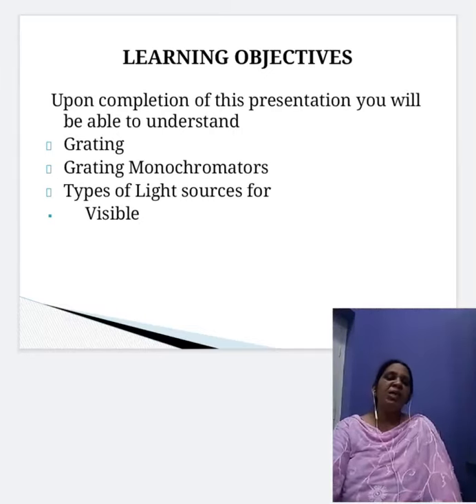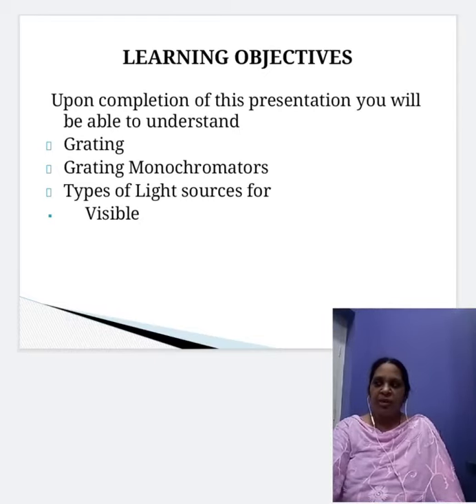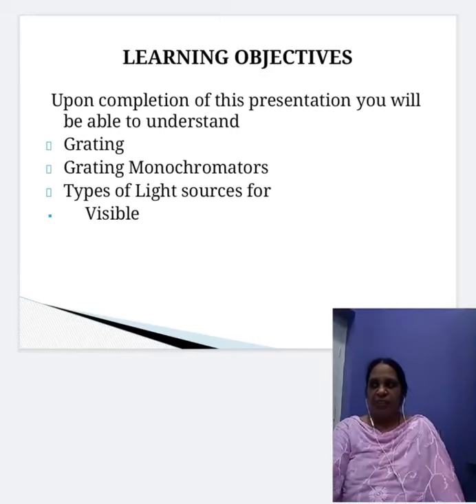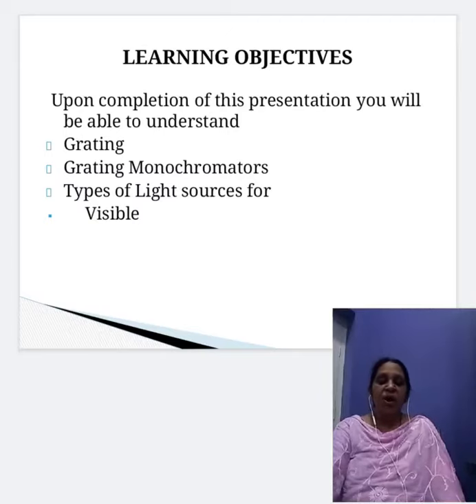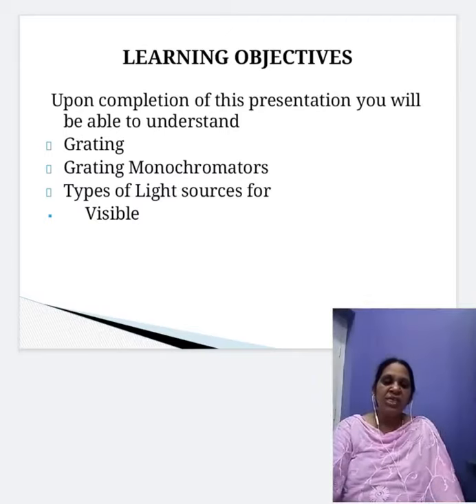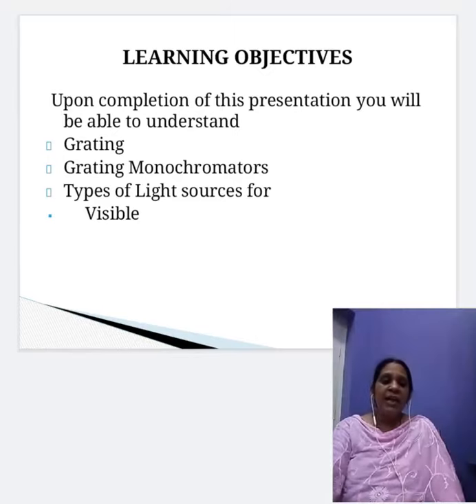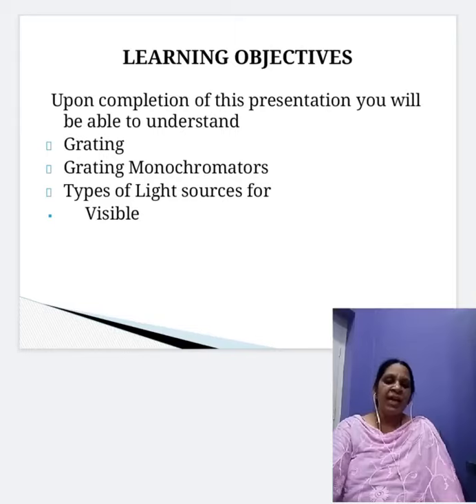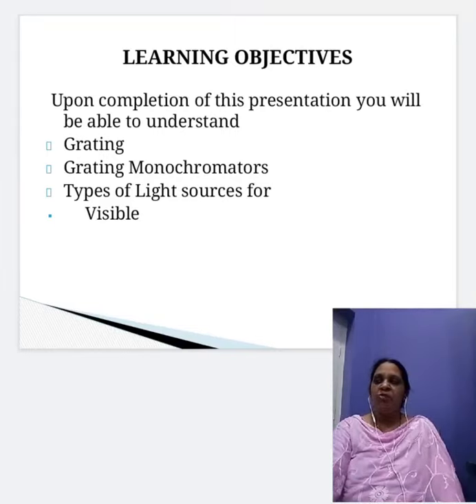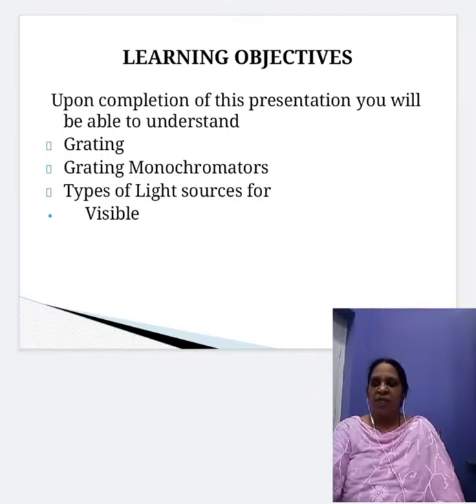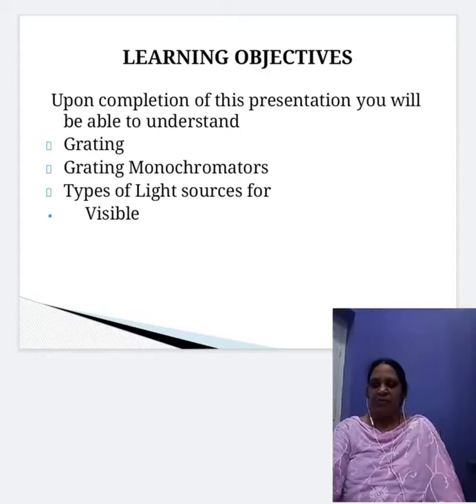The performance of a monochromator depends on the resolution, the light gathering power, and the purity of the light. Resolution is the resolving power of the monochromator — the ability to distinguish between separate adjacent spectral features. The monochromator must have very good light gathering power and purity of the light output. A monochromator must have large dispersion and high resolving power, which is necessary to measure the accurate emission spectrum.